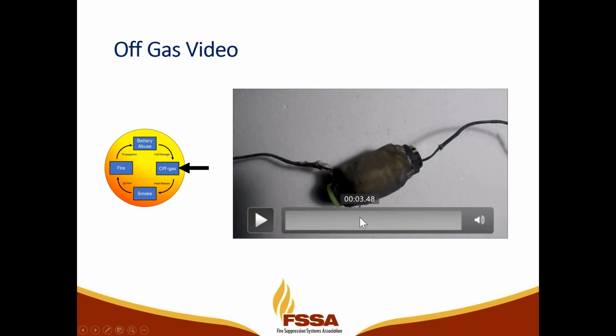This is an example of a cylindrical type battery being overcharged and then off-gassing. So you'll see here at the top of the battery, as we overcharge it, the battery will pop and off-gas right into this space right at the top of the battery here where the shadow is seen. You'll see like a sparkle or a moisture content pop out, and that's really where off-gas is going to be detected.